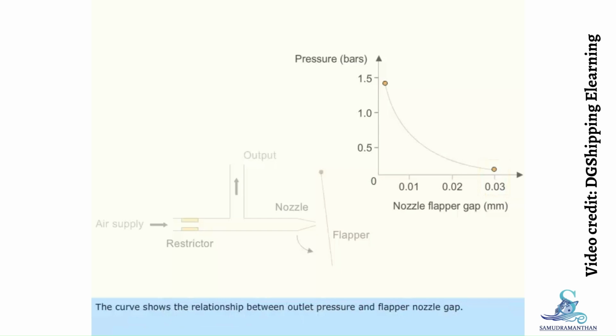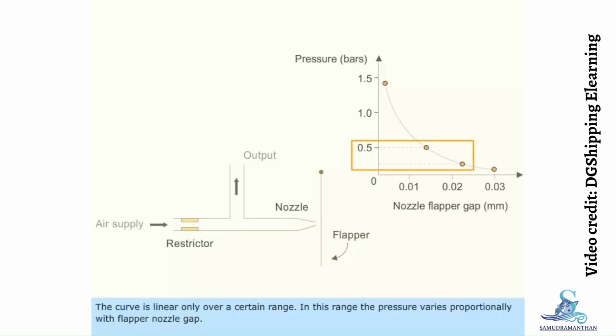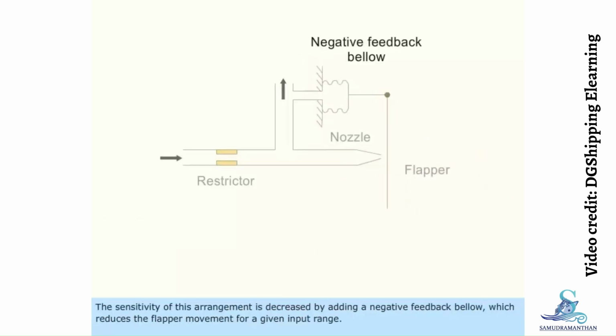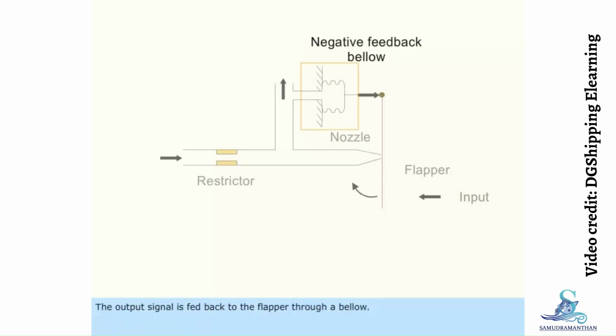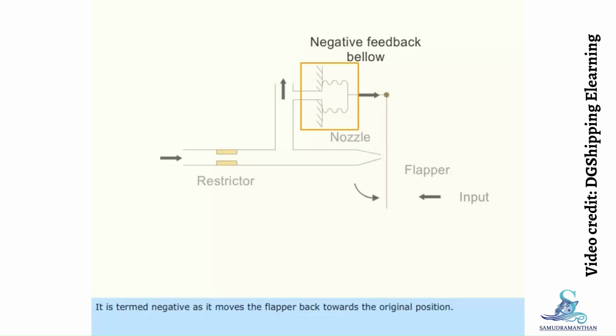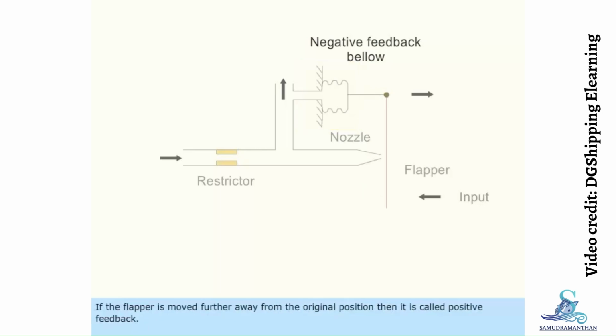The curve shows the relationship between outlet pressure and flapper-nozzle gap. The curve is linear only over a certain range. In this range, the pressure varies proportionally with flapper-nozzle gap. The sensitivity of this arrangement is decreased by adding a negative feedback bellow, which reduces the flapper movement for a given input range. The output signal is fed back to the flapper through a bellow. It is termed negative as it moves the flapper back towards the original position. If the flapper is moved further away from the original position, then it is called positive feedback.